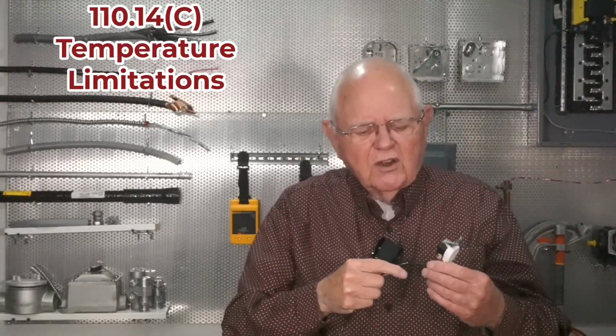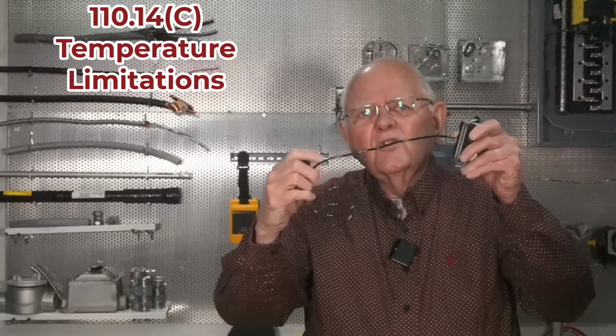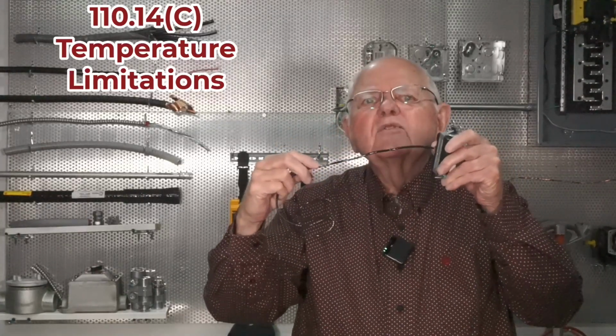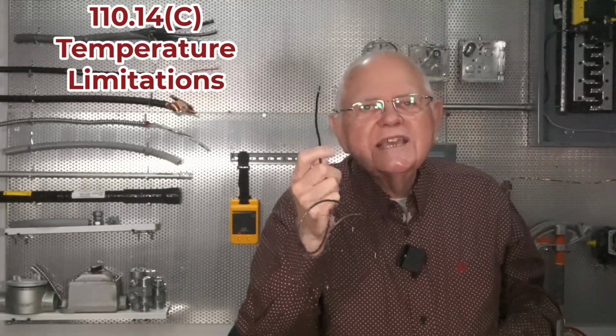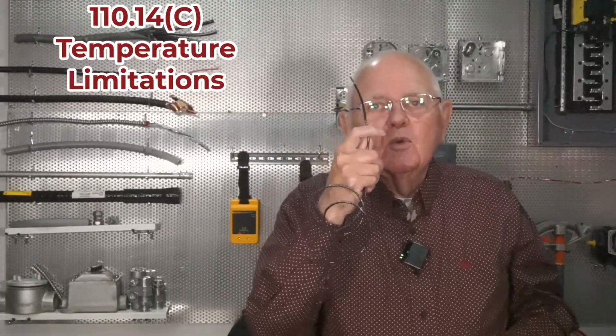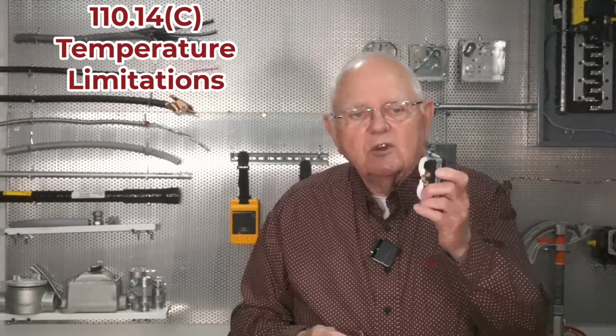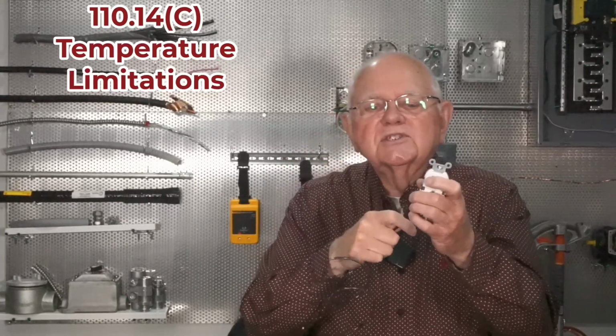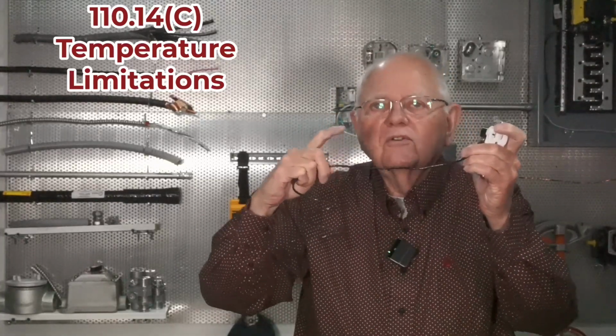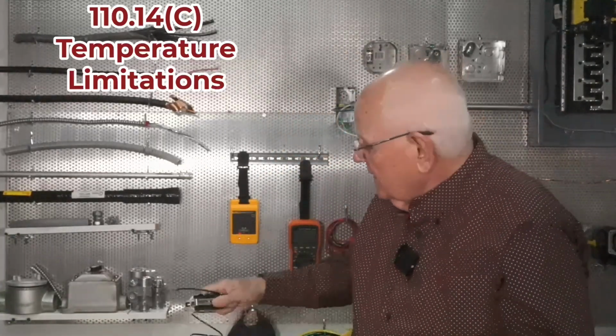I'll overheat my terminals. So what do I have to do? We used to use the term derate, but if I make my adjustment and correction factors, all of those types of things, I find out that I have to limit the current flow to this number 12 wire to 20 amps, because number 12 THHN in my 310.16 table says that the ampacity is 20 amps on that wire at 60 degrees C. So that way I won't overheat my terminal. I take my 30 amp wire, attach it to a 20 amp terminal screw, and have to limit the current flow through the wire to 20 amps so I don't overheat the terminal screw, right? That makes sense, and that's pretty much what 110.14(C) is addressing.